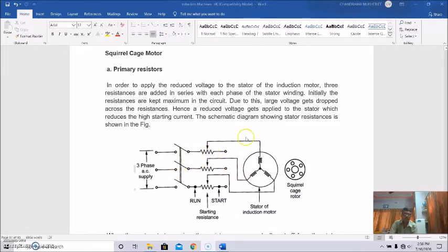See, this is the circuit diagram of a primary resistor starter for a squirrel cage induction motor. So what is the purpose of using these primary resistors or starter resistors? Basically, our main objective is to reduce the high starting current. I told you during our discussions that the high starting current can only be reduced by supplying reduced voltage to the motor terminals, that is, the stator winding terminals. So in order to apply this reduced voltage to the stator of the induction motor, three resistors are added in series with each phase of the stator winding.